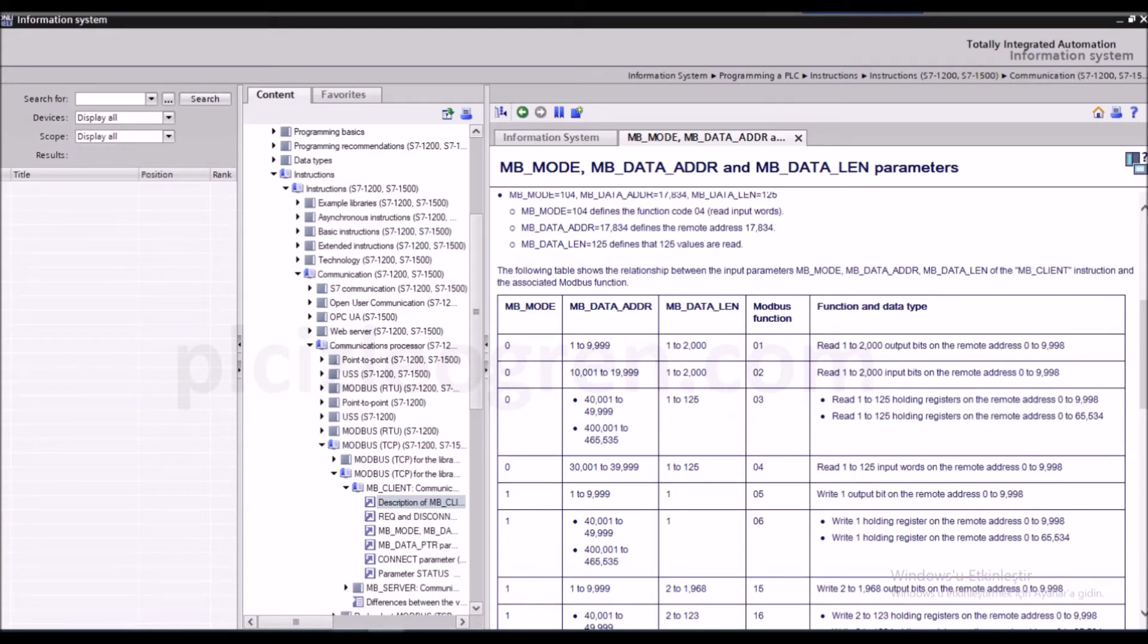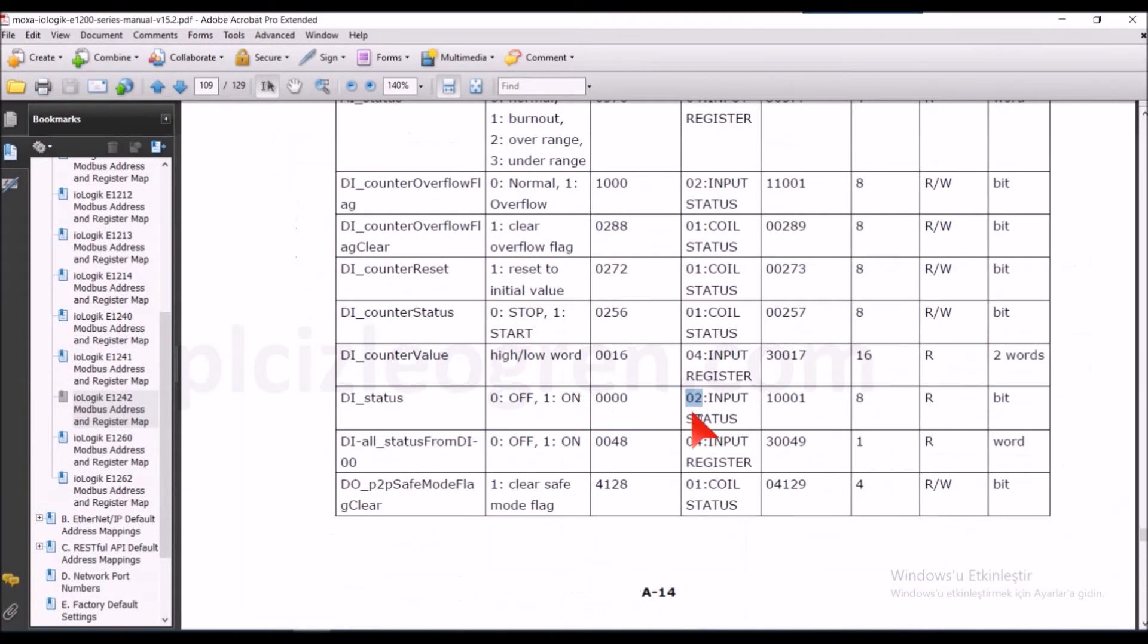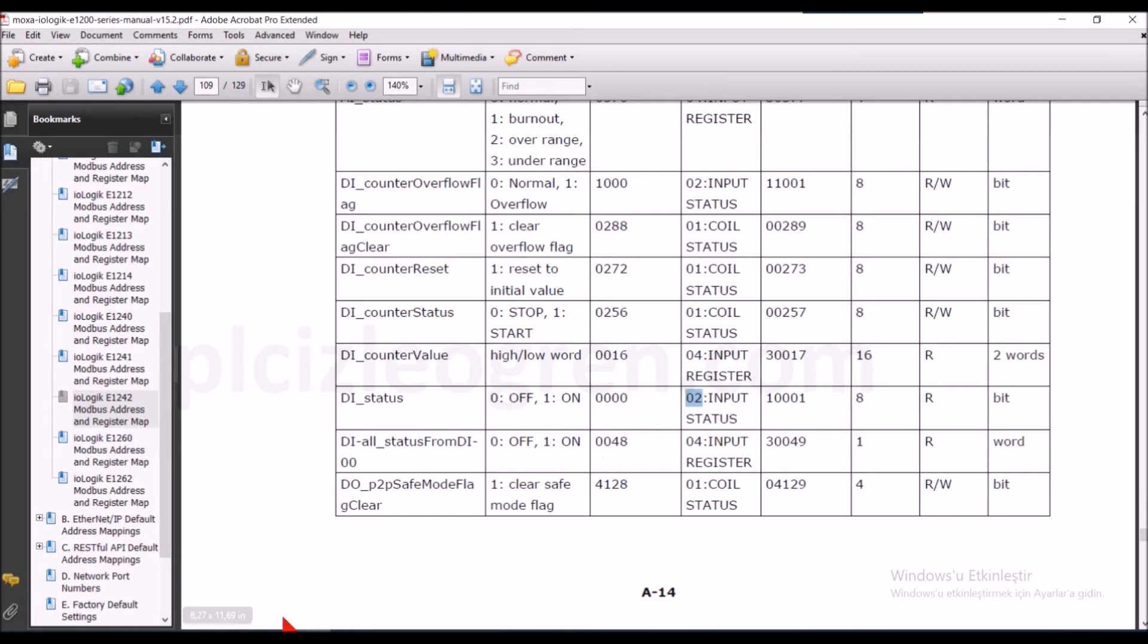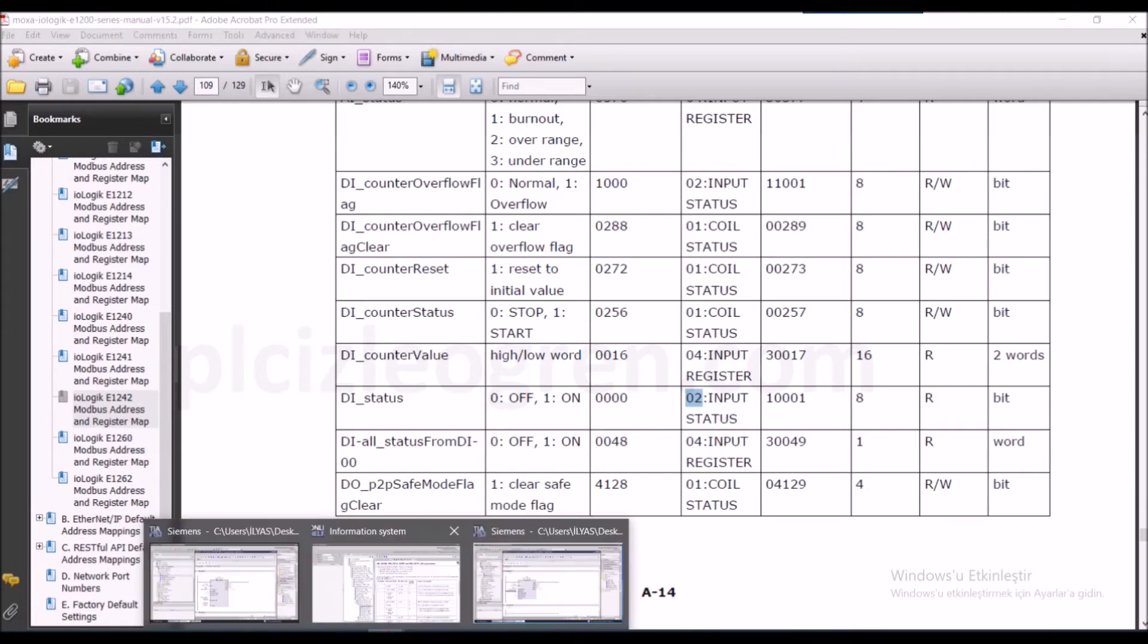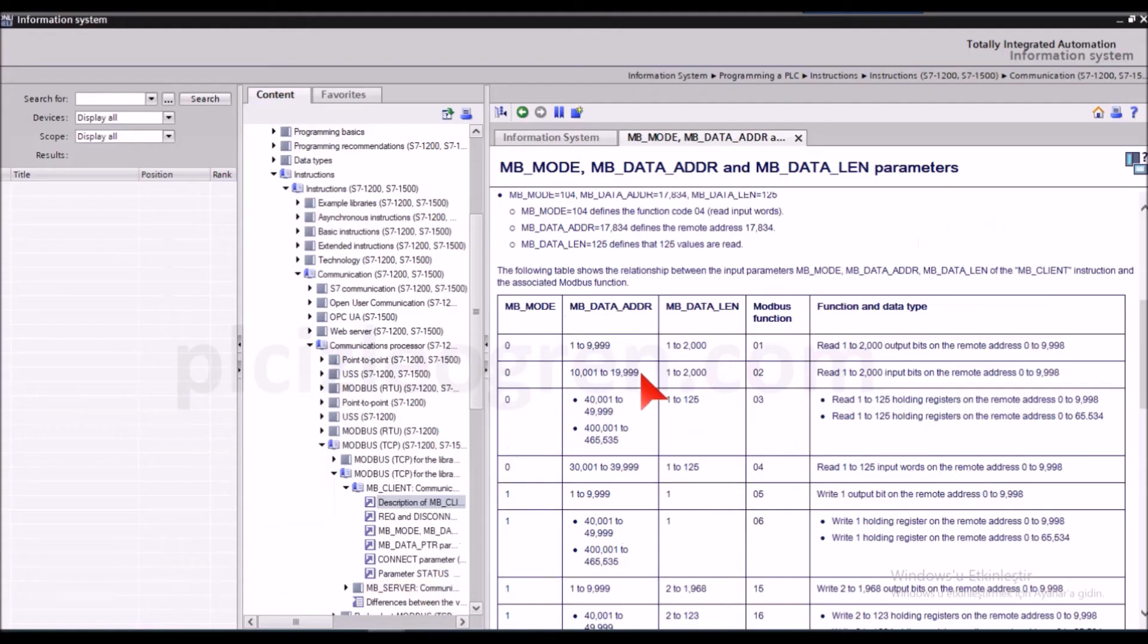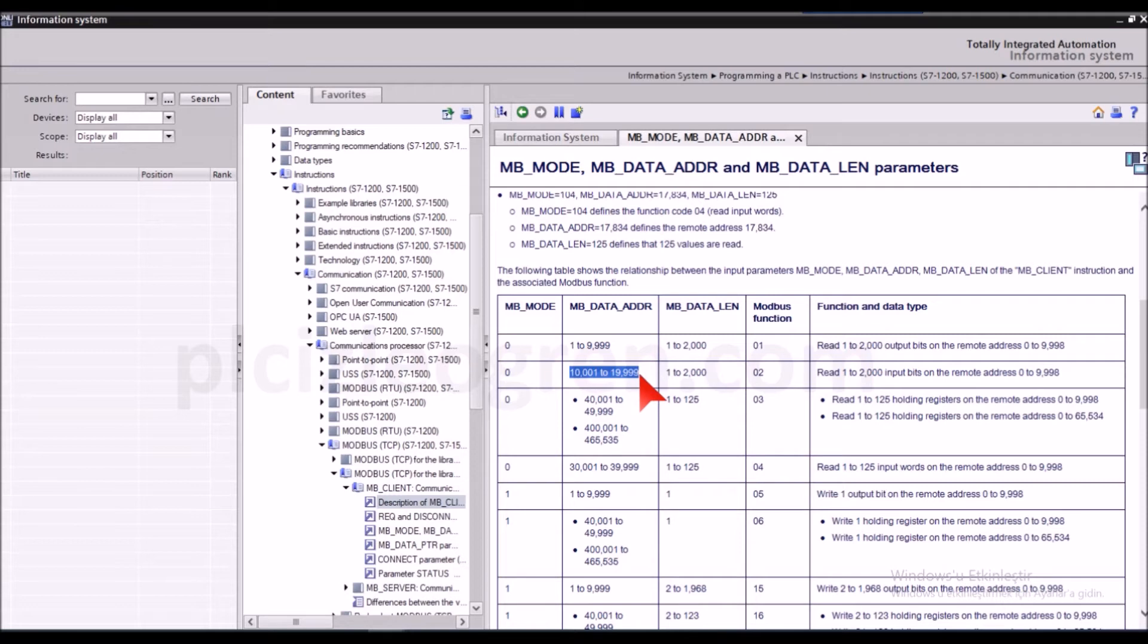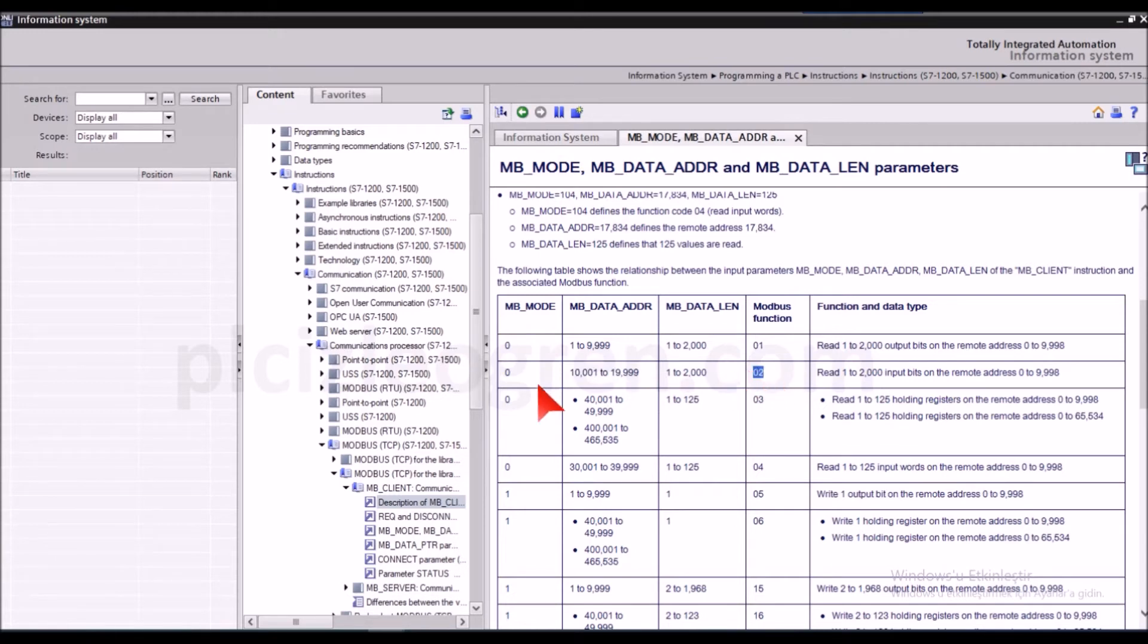So let's come here and as you can see we were using 10001 and the function 2, as you can see here. So let's see if there is anything similar here. Yes, yes there is. It says that if you are doing something between 10001 and 19999 and if you have an address and you are reading, then you'll use the second function and your mb mode will be zero. That's what I selected.